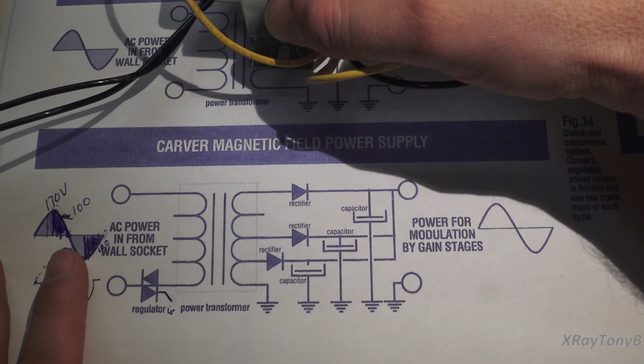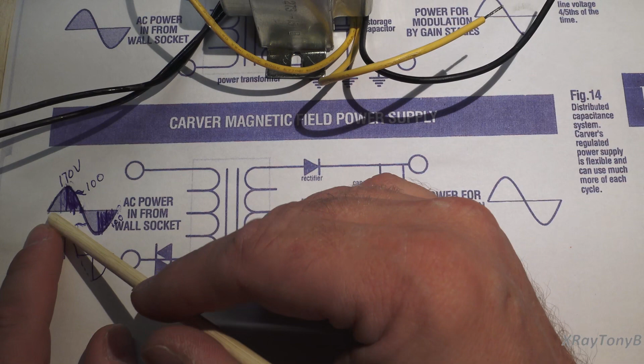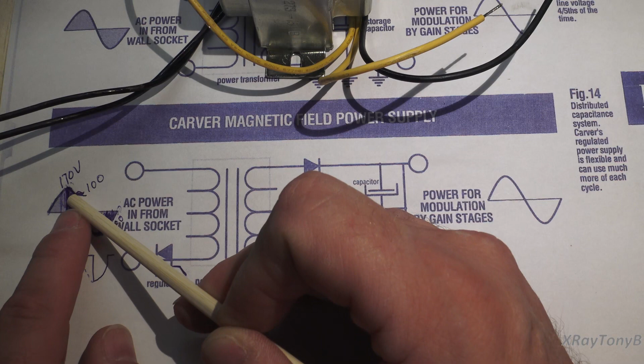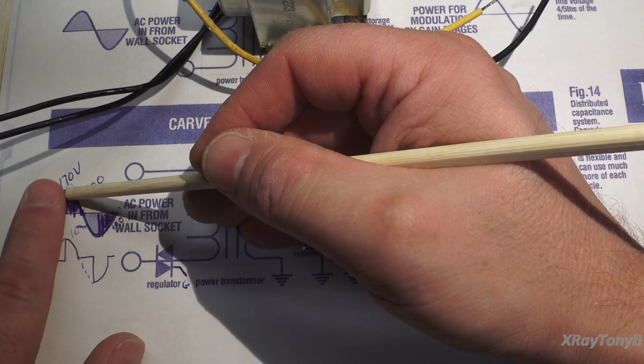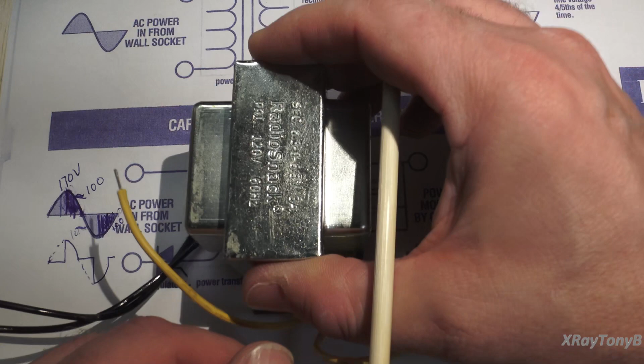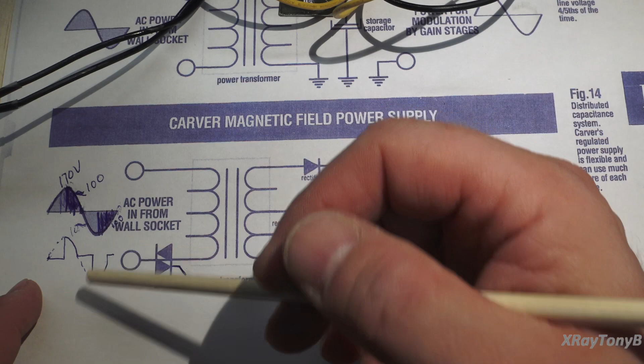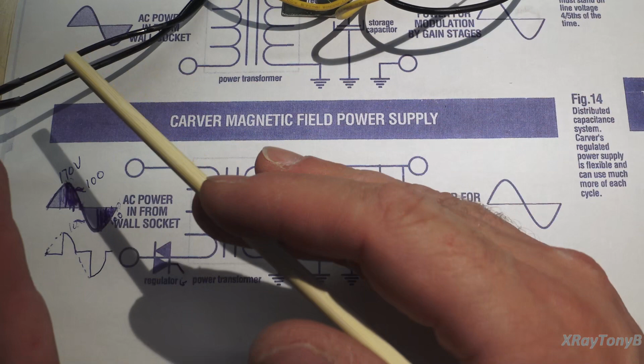One side effect of that is, instead of the transformer building up voltage and its magnetic field slowly from zero to peak and then slowly decaying back down to zero, if I turn this on all at once, I'm actually putting 170 volts right across the coil of this transformer, and for that split second it's going to draw really high current very quickly, for a short duration.